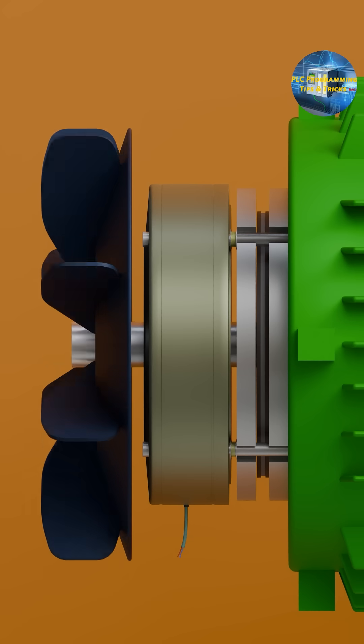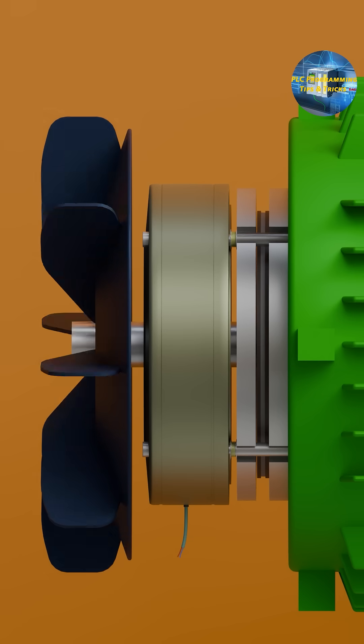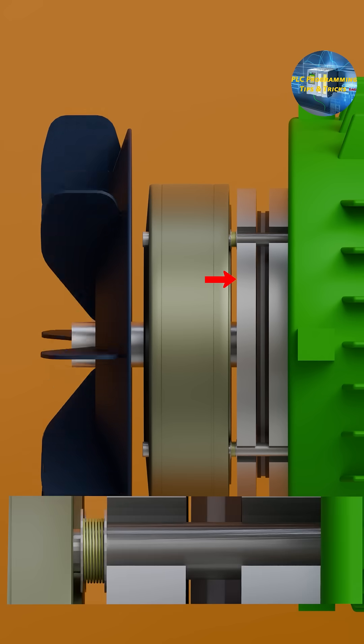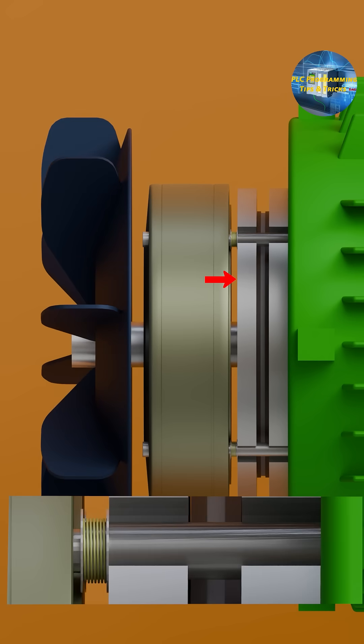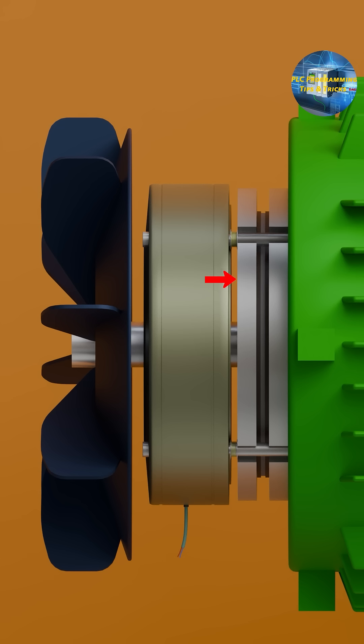When power is cut, the coil de-energizes. Instantly, the springs push the pressure plate against the brake pad, clamping it onto the hub. This friction force stops the shaft immediately.